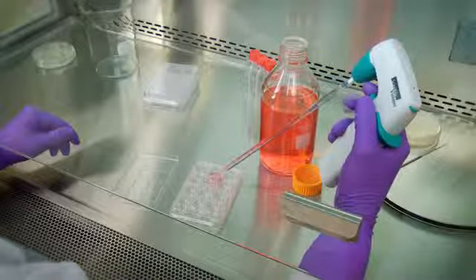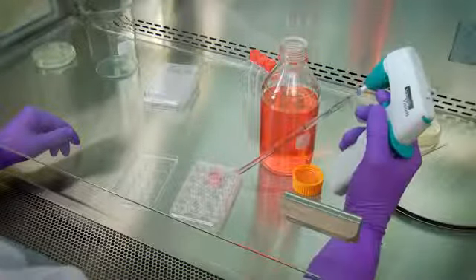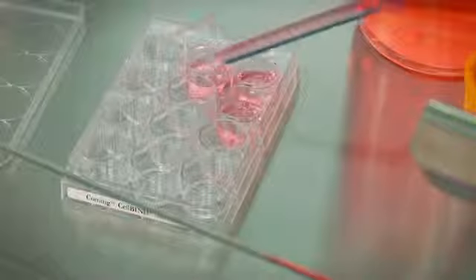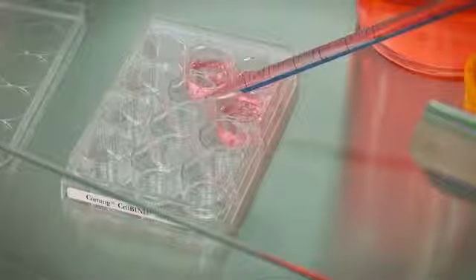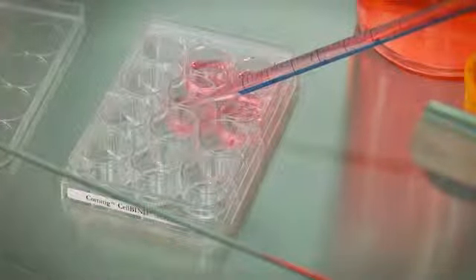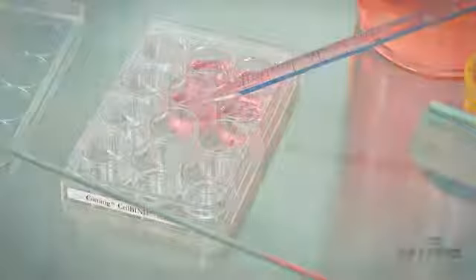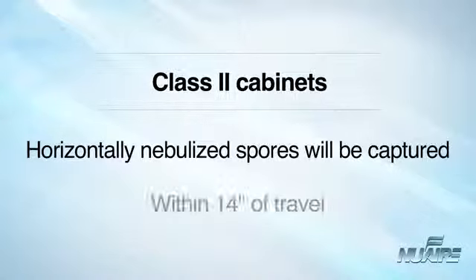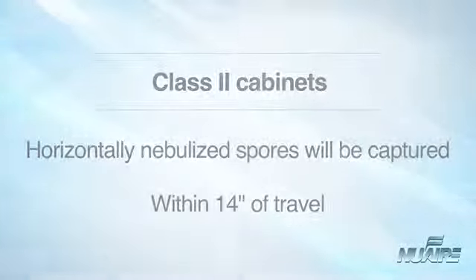For example, techniques to reduce splatter and aerosol generation will minimize the potential for personnel exposure to infectious materials manipulated within the cabinet. Class II cabinets are designed so that horizontally nebulized spores will be captured by the downward flowing cabinet air within 14 inches of travel.